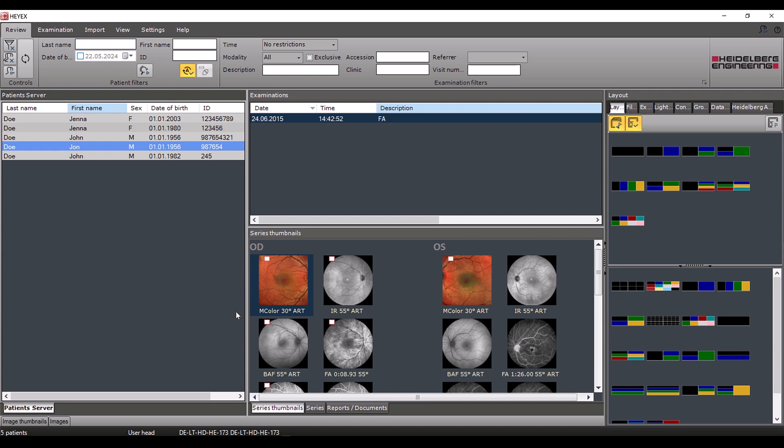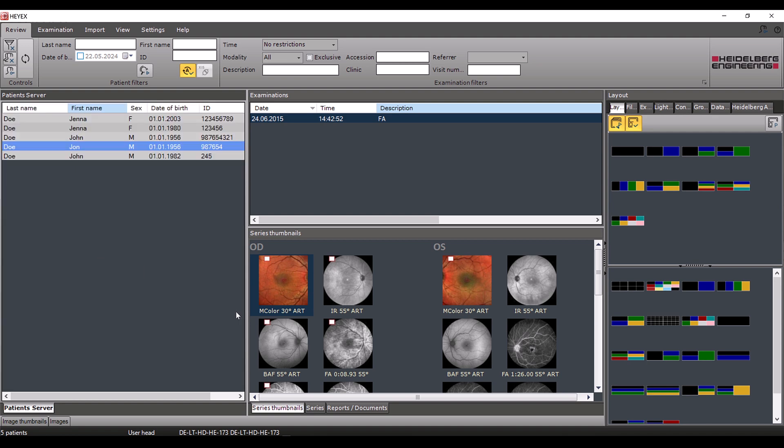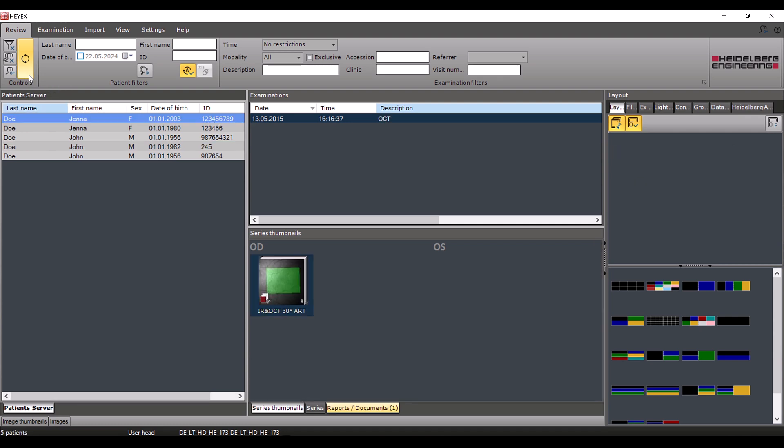Depending on the number of examinations and the size of the data set, it may take several minutes for the changes to take effect. Please always wait until the changes are displayed correctly before starting another procedure for this patient and do not make changes immediately before a planned examination. You can use the refresh button to reload the navigator view and check whether the changes have already taken effect.